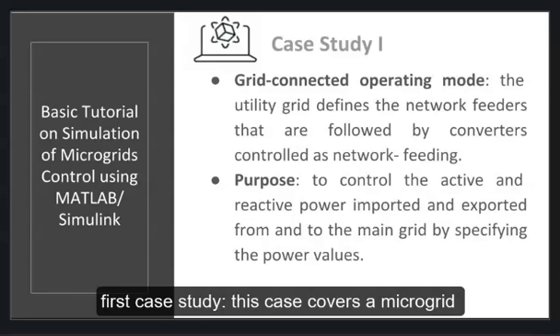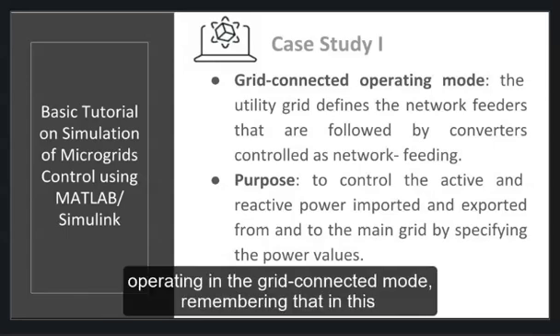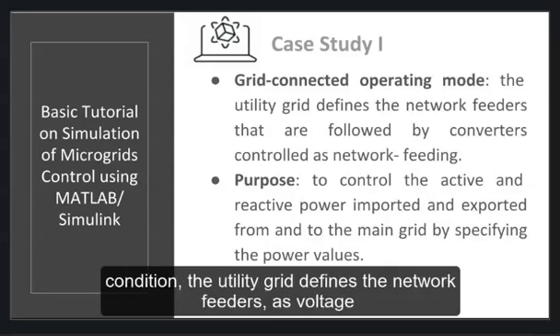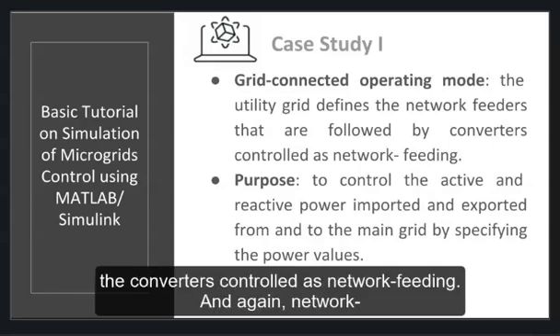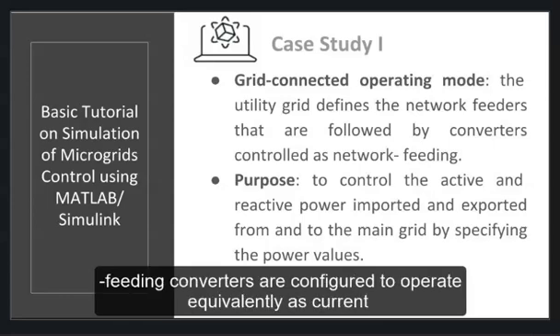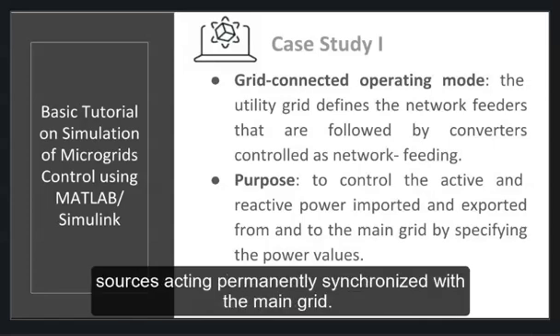This case covers a microgrid operating in the grid-connected mode. In this condition, the utility defines the network feeders as voltage amplitude, frequency and phase, that are all followed by the converters controlled as network feeding. Network feeding converters are configured to operate equivalent as current source, acting permanently synchronized with the main grid.